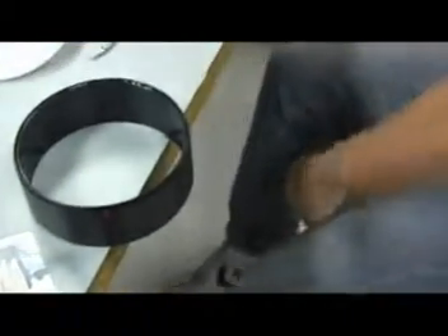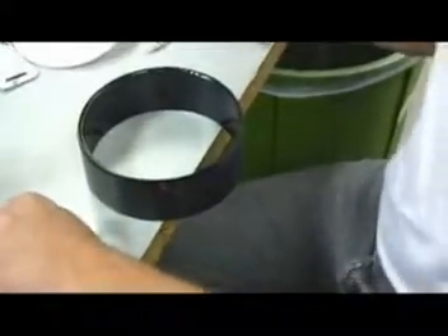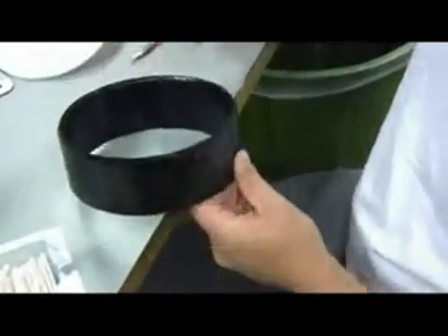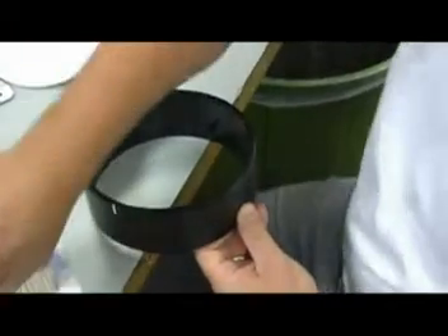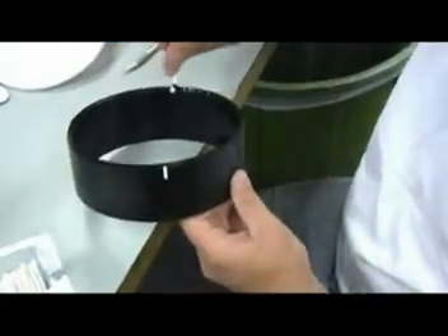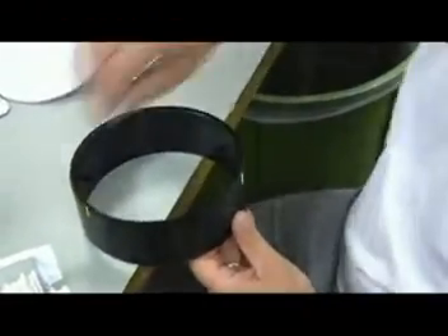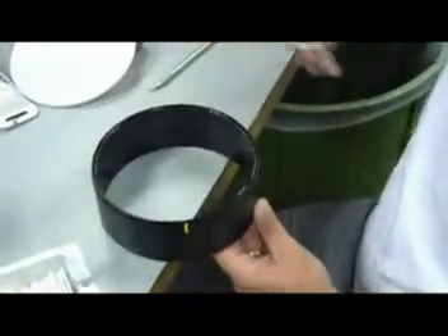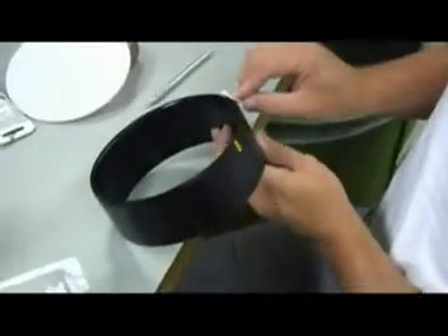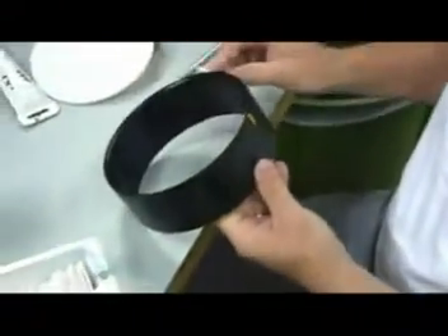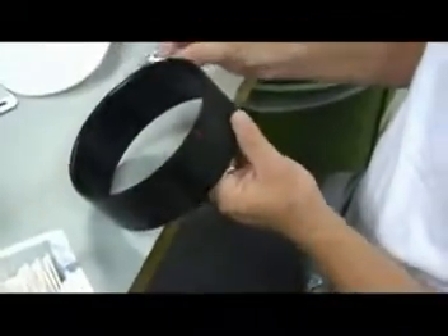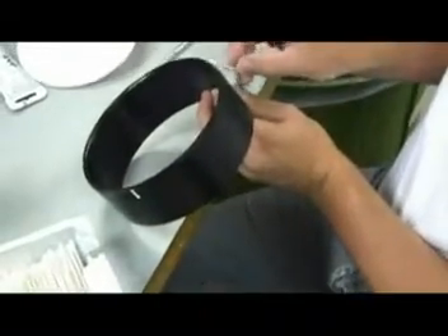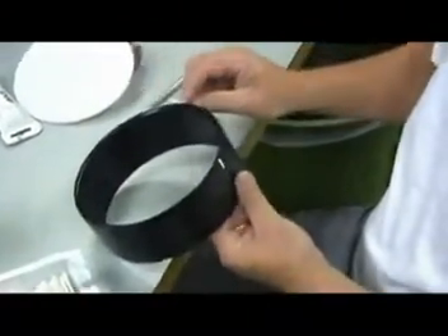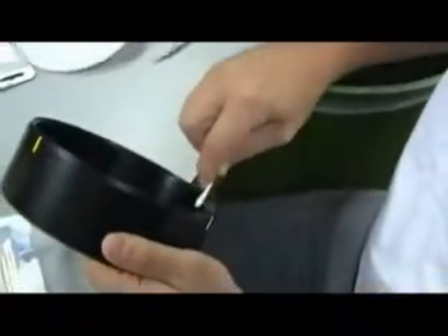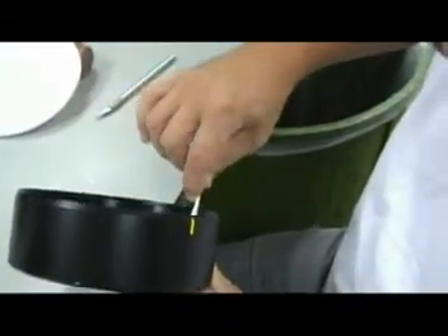For this step, I would get an entire box of Q-tips. We're probably going to use about 50 of them at least. What we want to do is hold the Q-tip at a 45 degree angle so it touches the bottom of the sample holder as well as the inside of the groove. Okay, and what we're going to do is take off the initial excess. So holding at a 45 degree angle, we'll go entirely around the inside of the sample holder. And now what we'll do is come around the outside of the sample holder and just get the bulk excess away. Okay, this is kind of where we're now doing the entire inside edge.